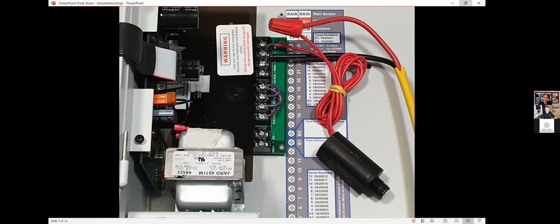Now, when I've connected the solenoid, I'll give you two answers. The short answer is it's tricking the controller, allowing us to use the transformer built into the controller to troubleshoot the two-wire path. The longer answer is it's putting about 30 ohms of resistance on that 2-wire path where it doesn't normally belong, reducing the amperage draw of our overcurrent issue.